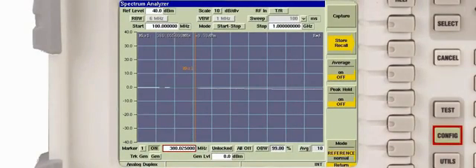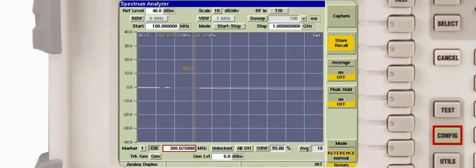The compensation value is programmed into the configure offsets tile, so we'll press the front panel config key to go to the tile.